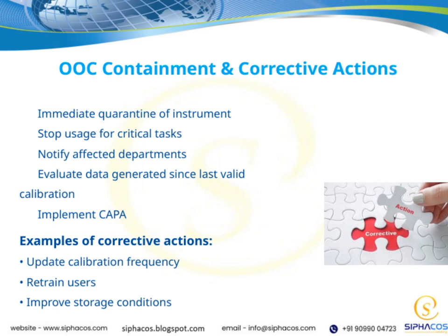Next, we evaluate the data generated since the last valid calibration to determine if there's been any impact or if further investigation is needed. Based on what we find, we implement corrective and preventive actions, or CAPA, to address the root cause and prevent recurrence.